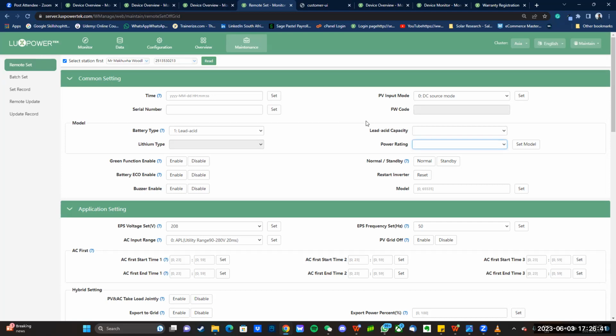The only difference is that if you select lead acid on the inverter, it will then ask you to pick the battery capacity. So after that, set model, restart, etc. Then your green function mode and your battery eco mode, I'm just going to explain what it reads over here. So the green function, when enabled, if the EPS load reading is lower than 60 watts for more than 10 minutes, the EPS output will cut off.